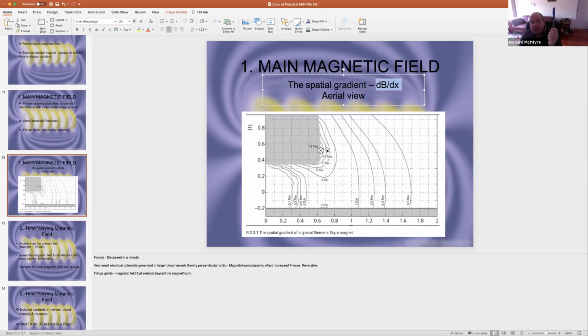okay, we know that if you put our ferromagnetic object next to the buttons of the gantry, so we're looking at the gantry from outside, this is the opening of the gantry, or the opening of the bore of the magnet. If you put our ferromagnetic object here, that's going to experience the greatest force in the whole room because it's up to 15 Tesla per meter. That's the change in magnetic field, which is relative to the force, the translational force on this object.